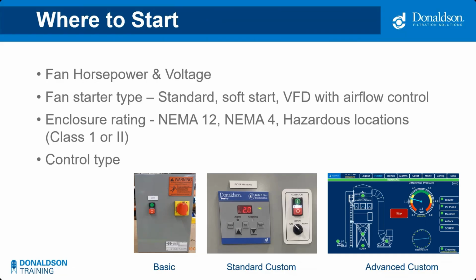First, you'll need to know the fan horsepower and voltage, which we talked about earlier. Then the fan starter type. Does the customer want a standard starter, which costs less but can be harder on the equipment and may produce higher utility costs on larger horsepower fans? Does the customer want a soft start, which ramps up the fan speed slowly, reducing wear and tear and utility costs? And are you specifying a VFD with or without airflow control? Usually they always have airflow control built into them.